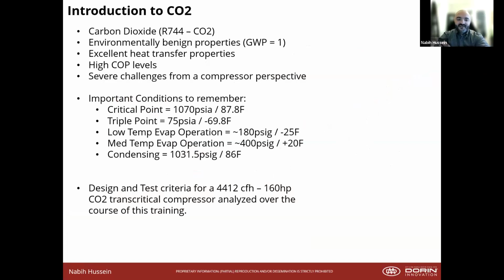So carbon dioxide, it could be called R744. It has a GWP of 1. That's because all other refrigerants are measured against it. So it's definitely a future-proof, sustainable refrigerant. Has excellent heat transfer properties, high COP levels, and some would describe it as the perfect refrigerant, but it does have severe challenges from the compressor perspective and some of the other components.